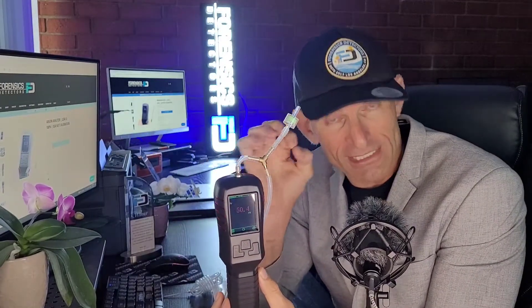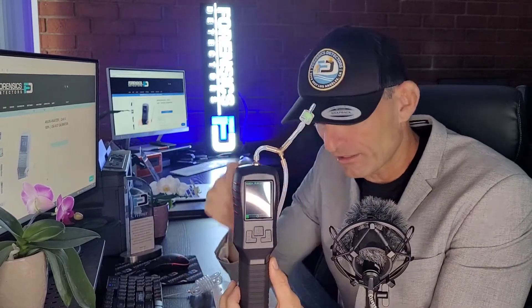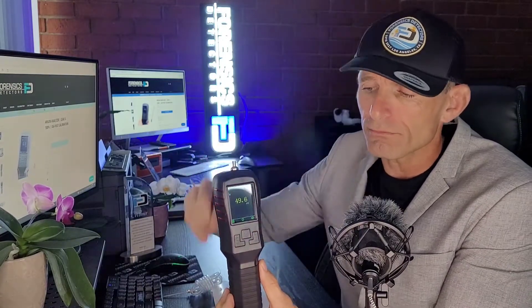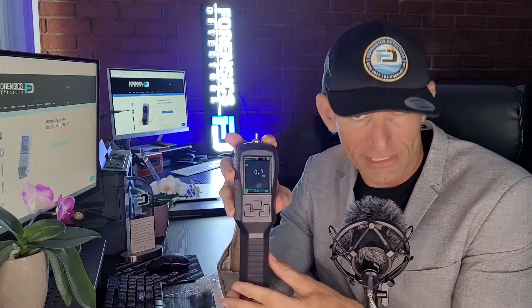50.1, 50.2 — extremely sensitive indeed. The thermal conductivity sensor is extremely accurate; it's an amazingly accurate analyzer. You can turn on and off the pump at will just by pressing the left button. It's very versatile, and all the functionality — calibration functionality, alarm functionality, and even some graphing functionality — is all in this little package.